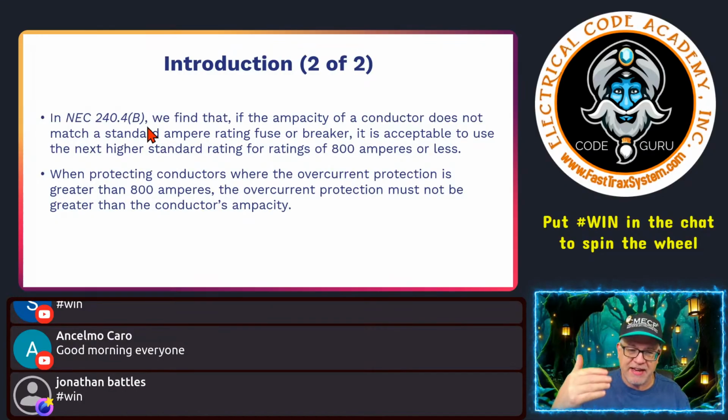It's just not in the table. So I could go to the 30 and not have to go to the non-standard 25. That's kind of how it works, okay? Most of us just go to the standard size and it's considered fine. You always have to make sure that your conductor, though, can handle the load. So got to do a load count.